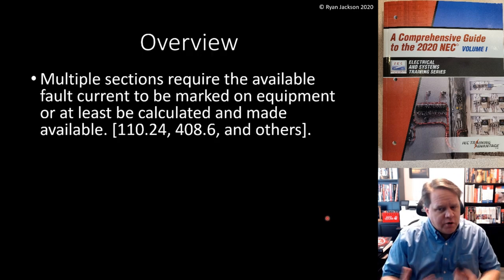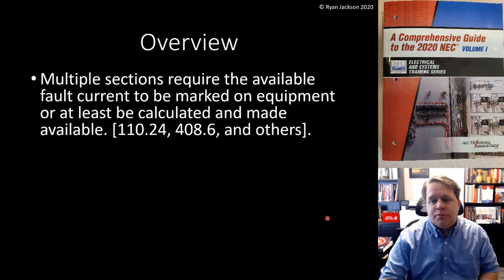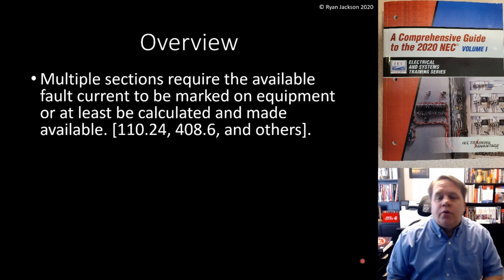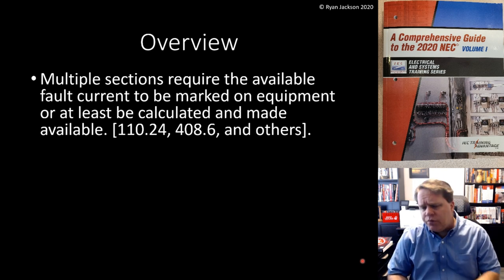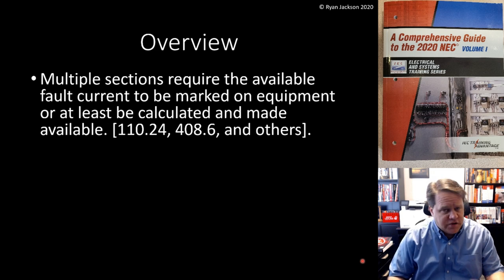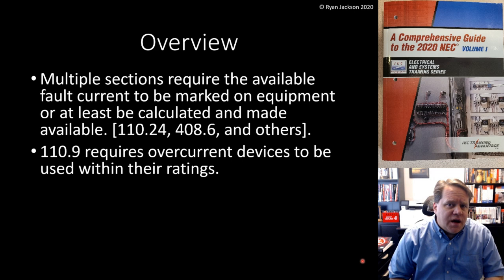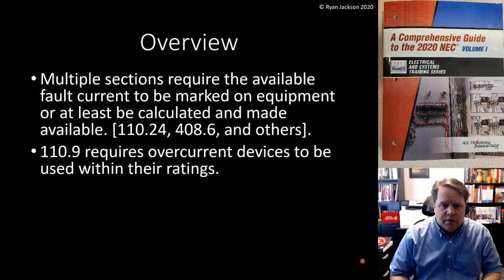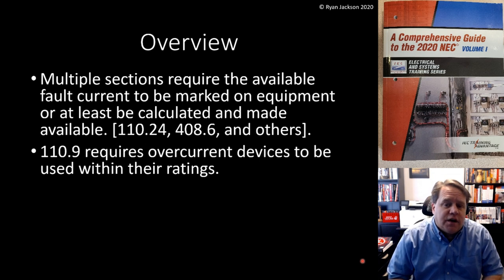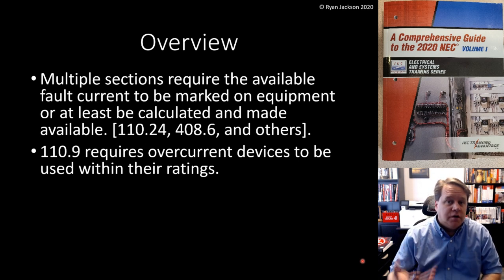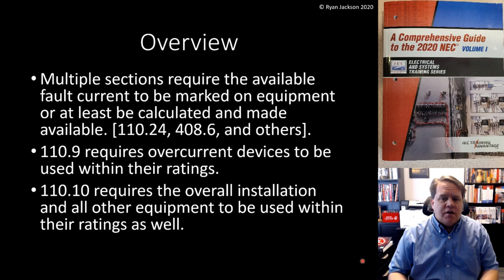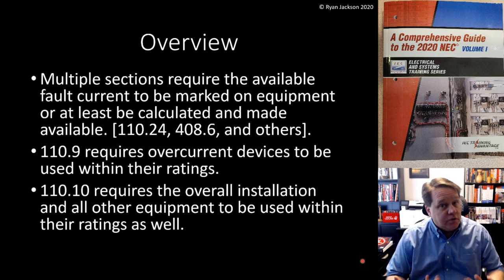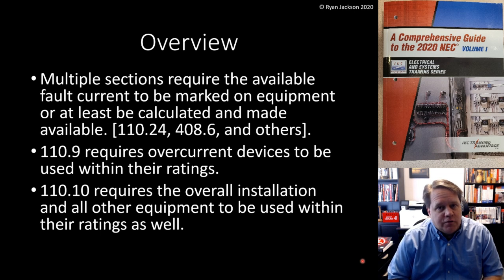So the overview - why do we need to talk about this? What are the code rules pertaining to these issues? Multiple sections require the available fault current to be marked on the equipment or at least be calculated and made available to those that need it: 110.24, 408.6, and others. 110.9 is where we really get into the safety requirements, and that requires that overcurrent protection devices be used within their ratings - we're going to call those interrupting ratings. And 110.10 requires that the overall installation and all other equipment must also be used within their ratings as well.